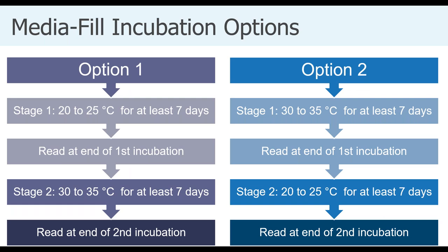There are two media fill incubation options. Following feedback on the earlier version, the chapter now allows you to start at either 20–25°C and transfer to 30–35°C, or vice versa—the order is your choice. Ensure you read samples at the end of both the first and second incubation periods.